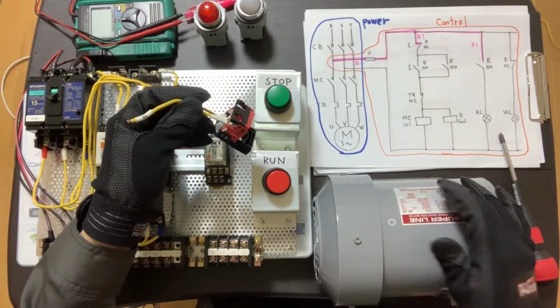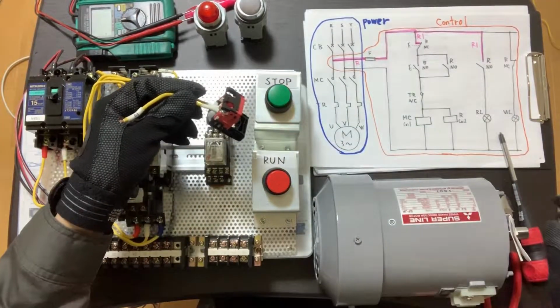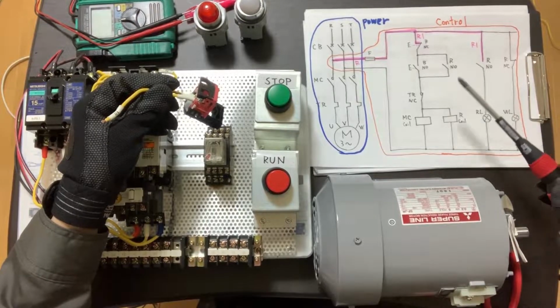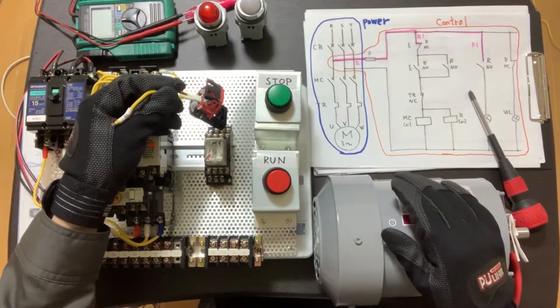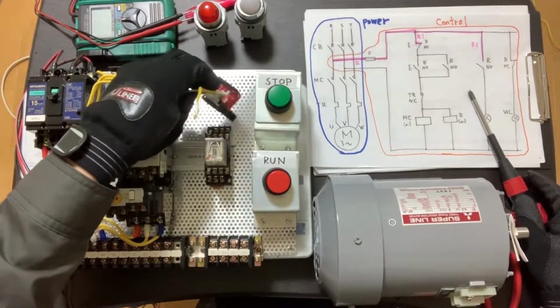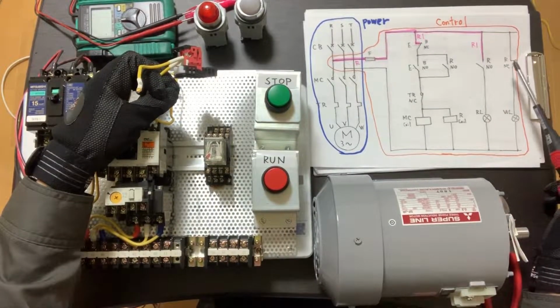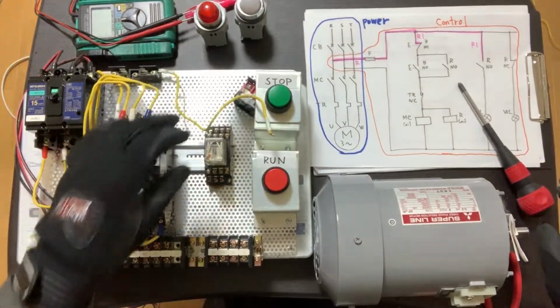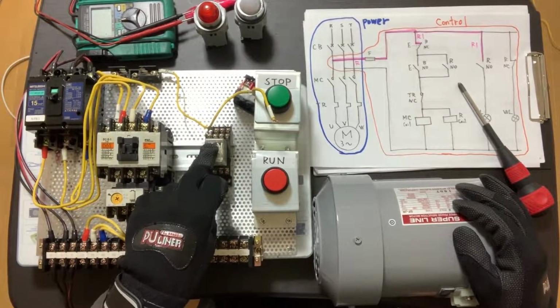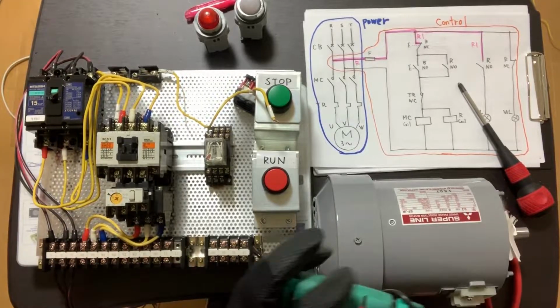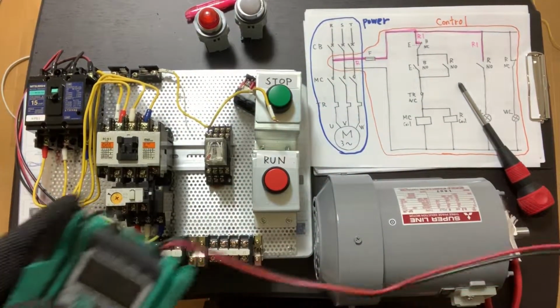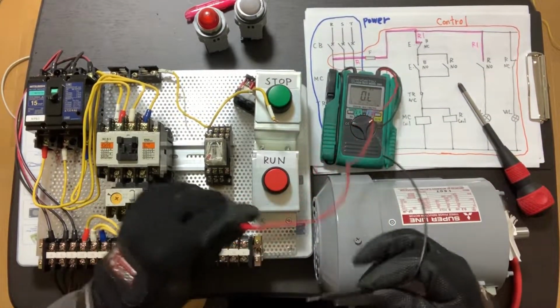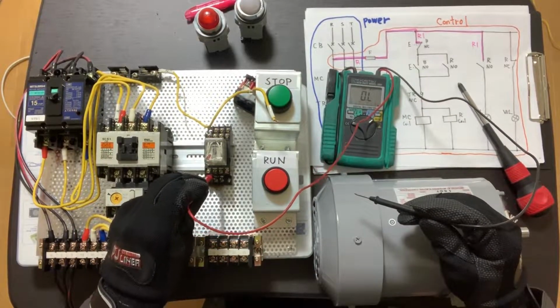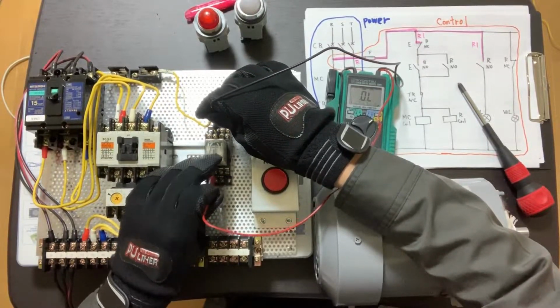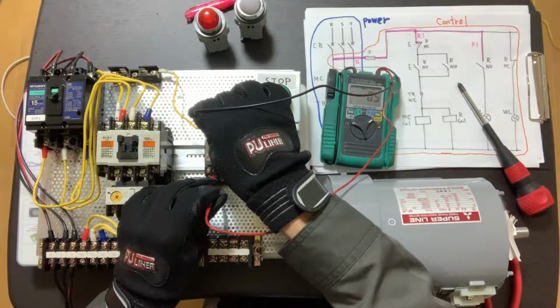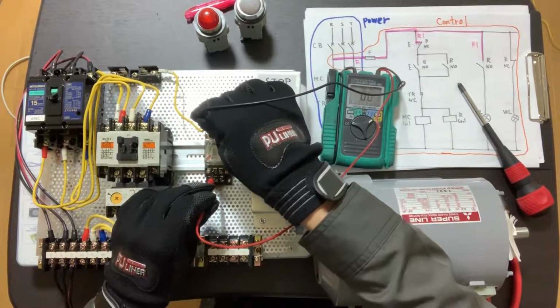And be careful when you connect a device which has contacts, like a relay. You should be sure whether the terminal you are trying to connect is normally open or normally closed. If you are confused about the state of the contacts, you can check with a multimeter in the resistance range. Normally closed is always 0 ohm, and here it beeps like this, and a normally open contact is infinity.